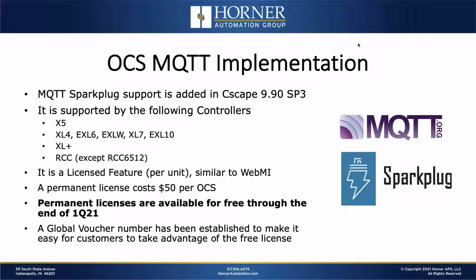Okay, now getting to the OCS implementation of MQTT, a couple notes here. What we are currently supporting is MQTT Sparkplug, and that was added with Cscape 9.9 Service Pack 3. It's supported by all of our mainstream XL series controllers, plus the X5 model, which is part of the micro series, but that's the only micro series controller that supports MQTT. And then the XL Plus and the RCC series, except for the RCC 6512, all those products support MQTT as a client.